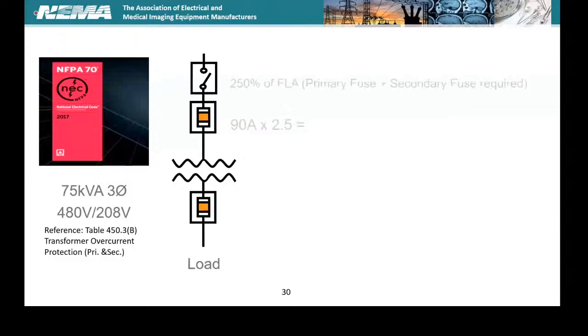So in this case here, we have a primary fuse, but we also have a secondary fuse. So we can increase the primary fuse to 250%. We've got a 225 amp fuse. And on the secondary, we go 125%. So we got 208 times that, and that'll give us the 260 or the next available frame size up. And we did not pick the fuse on that case there, but go to the table, you get the next available frame size up on that fuse size.